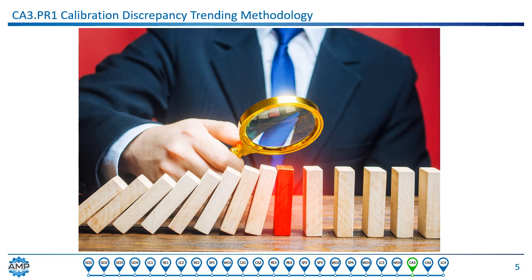Ideally, there should be no such thing as a planned deviation, but in real life, situations do arise that require evaluation of the effect on product quality. For instance, a long process could prevent access to an instrument with calibration lapsing before the process is completed. In this case, a planned deviation or calibration extension would be initiated. The approval of such a deviation is based on statistical data that shows the calibration history and the drift rate could extend beyond the due date of the instrument with a reasonable risk that it would not fall out of process tolerance, if continued to be used.